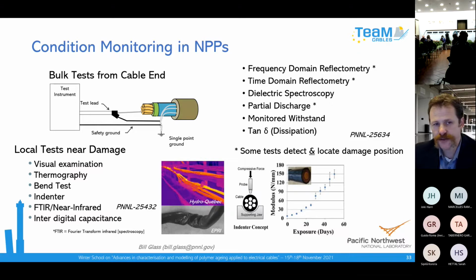So definitely the move is towards online monitoring, and a step in that direction is just being able to test cables while minimizing the number of disconnects that occur. So we've been looking at that currently at PNNL, testing cables connected to the motor or not connected to the motor, and trying to understand the signals from those tests in those scenarios.